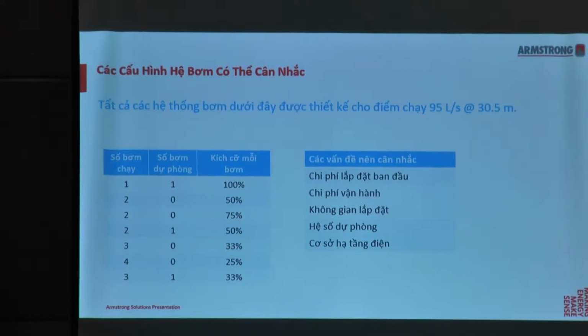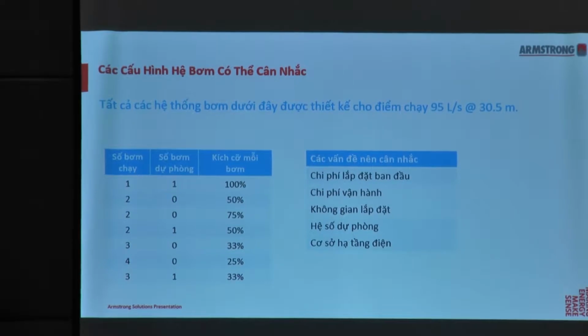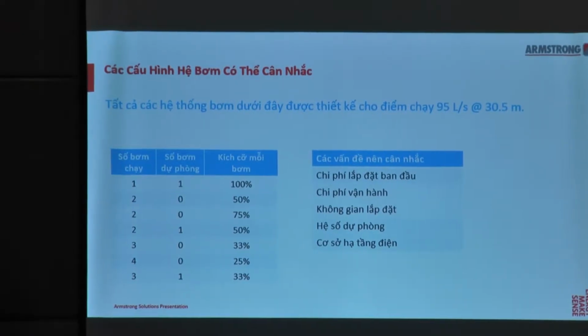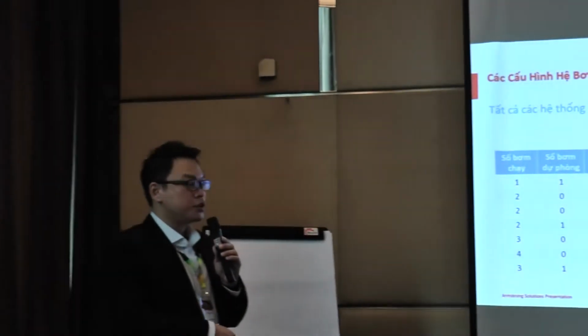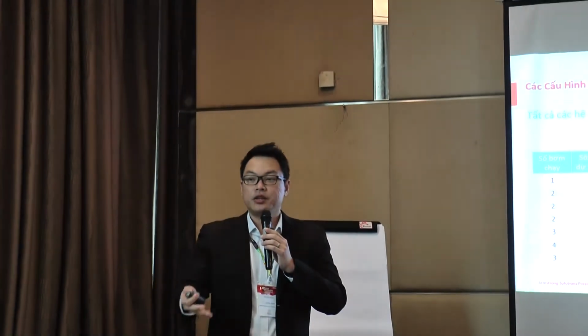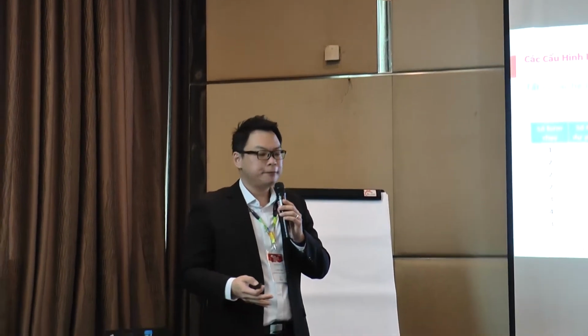Okay? And if you were to do, just to pick one example, let's say 2 pumps. With 2 pumps, you can have 3 types of combination, right? One is 1 duty, 1 standby, each sized for 100% capacity. Or you can have 2 duty, each sized for 50%. Or you can have 2 duty, each sized for 75% capacity split. And the factors that influence which option you should use are all listed on the right-hand side here.